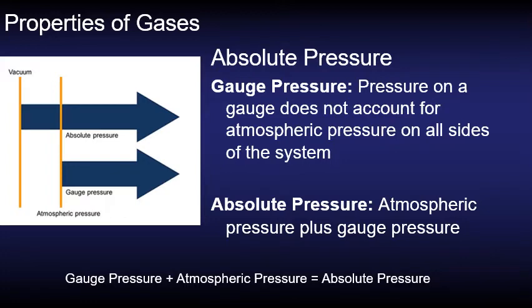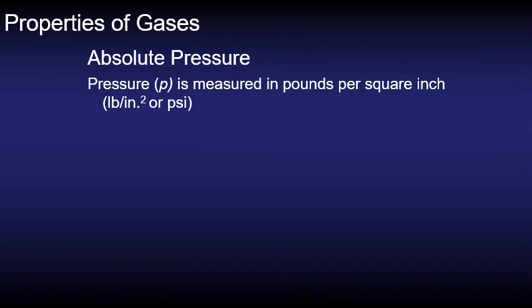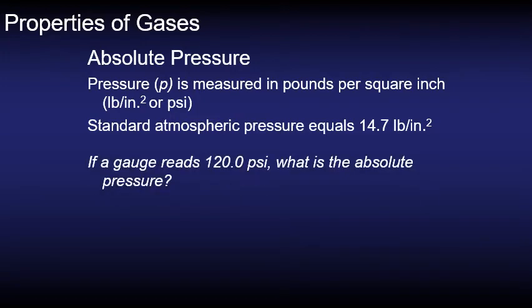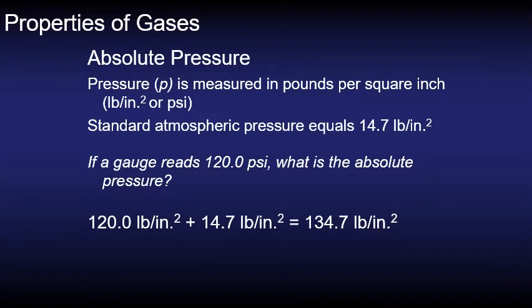So how do we calculate absolute pressure? Pressure in general for pneumatics is going to be calculated in pounds per square inch or psi and we are always going to use 14.7 psi as our standard atmospheric pressure. So if a gauge reads 120 psi what is the absolute pressure? The calculation is just to add the gauge pressure to the standard atmospheric pressure of 14.7 and so in this case it would be 134.7 psi.